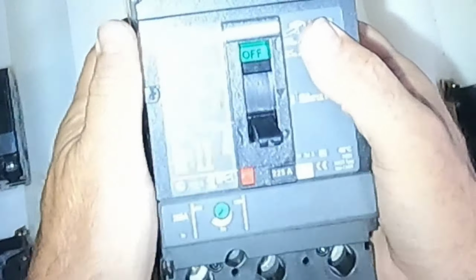So this is rated at 250 volt, 20,000 KAIC. But look, it goes up to 65,000 at 240 volt and only 20,000 at DC. And these are, to me, the best. And look, it's rated here 250, 500 volt DC, interrupting KA 20,000. This is an expensive breaker. You wouldn't get this breaker new, but if you have it laying around, you could use it. It's a very good quality breaker. If you're trying to do a really quality install, you use products like this. Look at that. DC in, DC out. That's perfect for a nice battery bank. In fact, I'm going to use this.